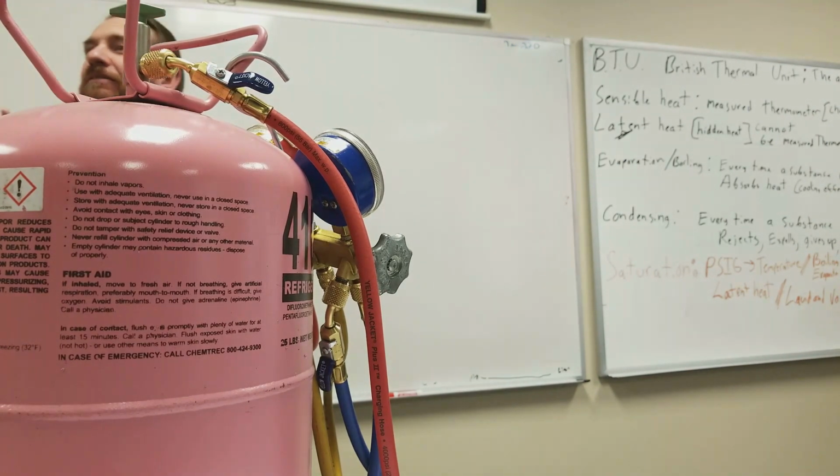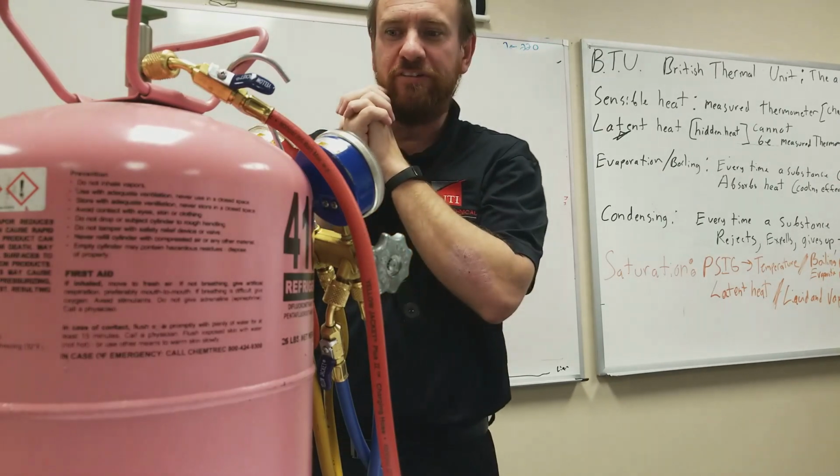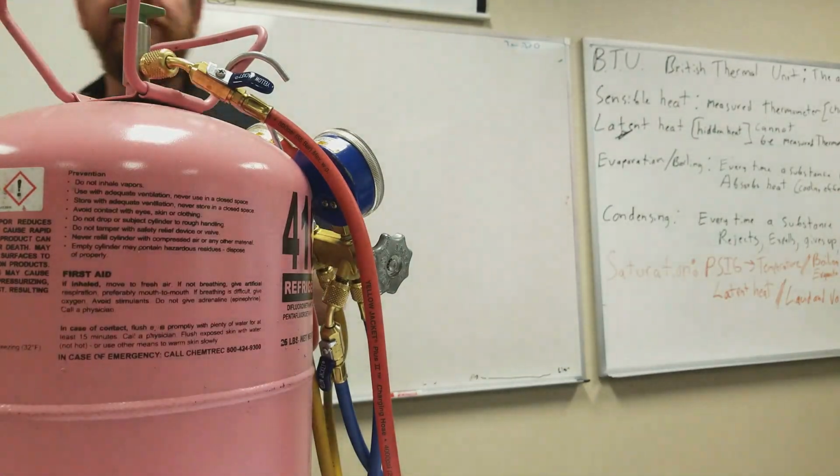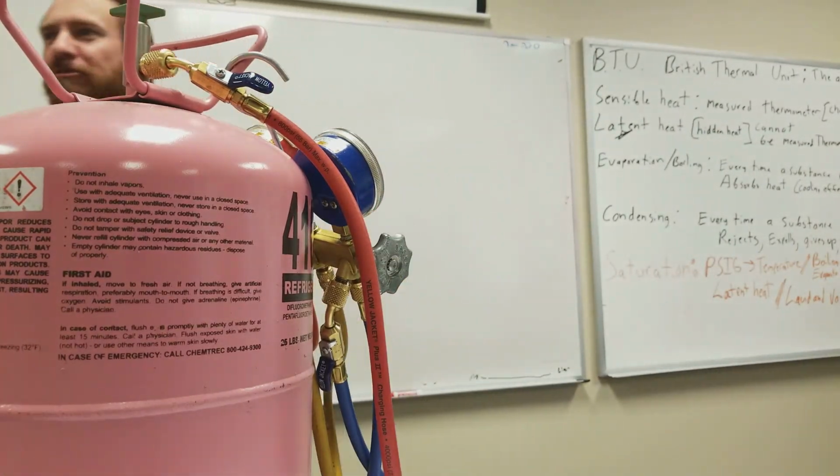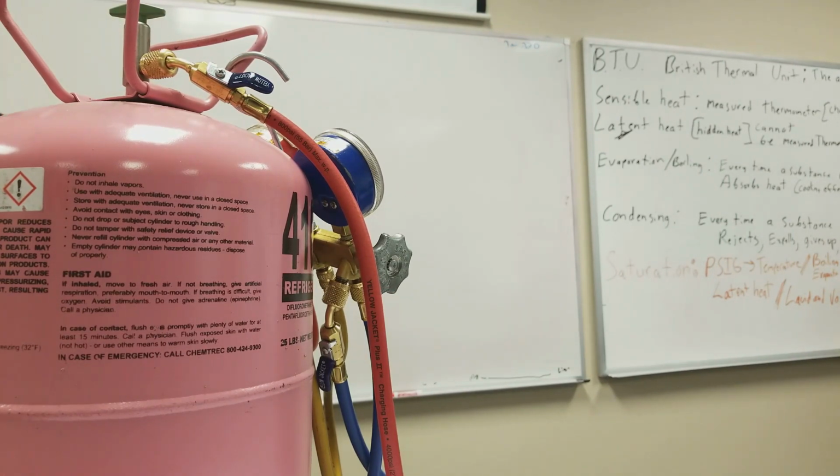102. 410A. 72. Oh, 410? 410A. Yep. 72 degrees Fahrenheit. So what do you think the temperature of that refrigerant is, if it's liquid and vapor? 72 refrigerant, so 72 degrees. Let's see what the temperature of the room is. Well, it's 70, so we're pretty close.